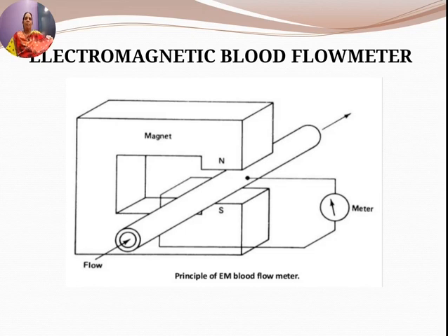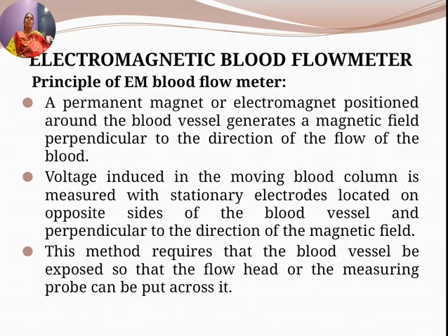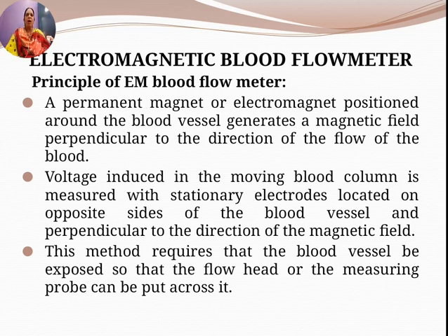In the construction of the electromagnetic blood flow meter, a permanent magnet with north and south poles is positioned around the blood vessel and blood is allowed to flow through the vessel. The permanent magnet generates a magnetic field perpendicular to the direction of flow of the fluid.